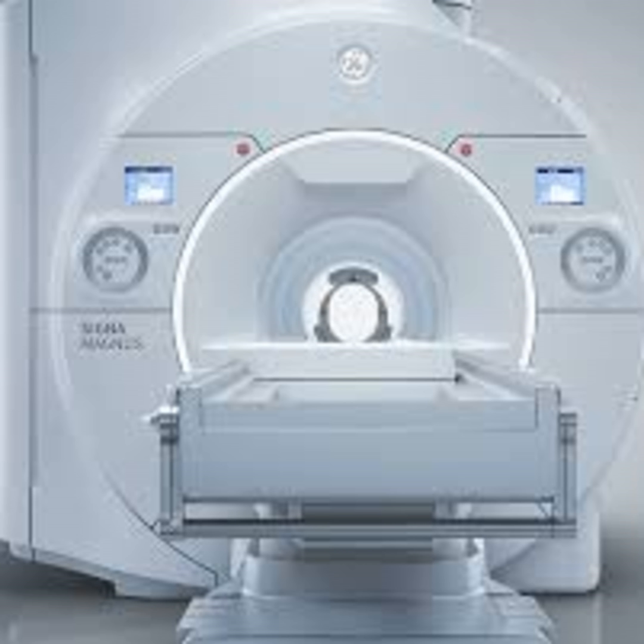In the field of modern medicine, few tools are as impressive or as intimidating as the magnetic resonance imaging scanner, or MRI. These machines house superconducting magnets cooled by liquid helium that generate fields ranging from 1.5 to 3 Teslas. To put that in perspective, a 3 Tesla magnet is approximately 60,000 times stronger than the magnetic field of the Earth. Given that a compass functions by aligning itself with the strongest ambient magnetic field, a logical question arises. Why doesn't every compass within a several block radius of a hospital point directly toward the radiology department? Today, we explore the principles of field decay and the sophisticated engineering that keeps these massive forces contained.